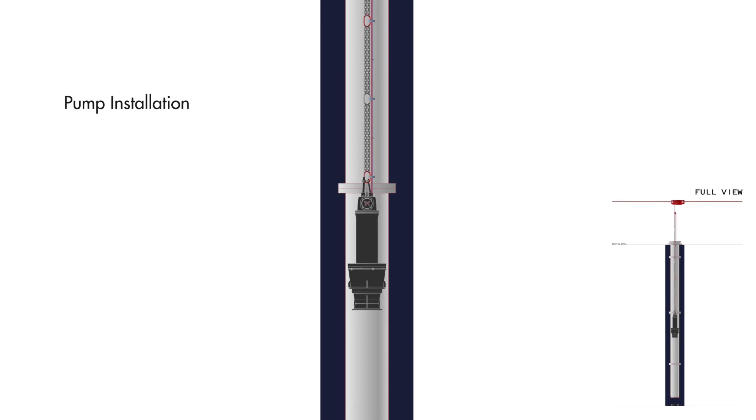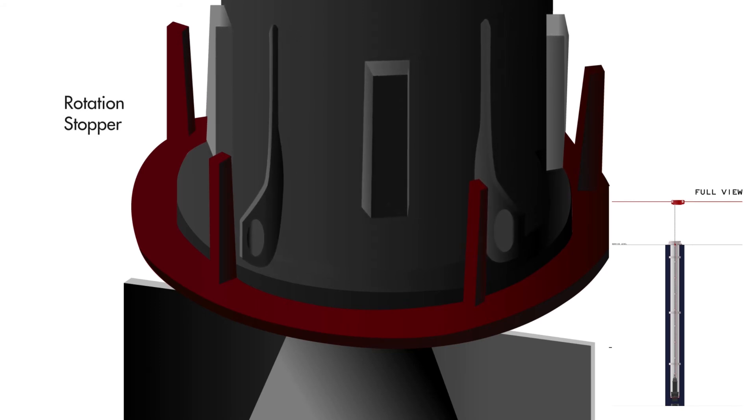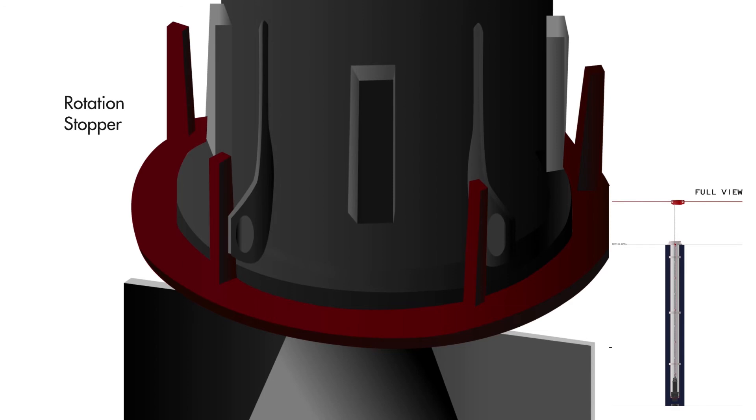With the pump almost in place on the seat ring, rotate the pump clockwise until the rotation stoppers on the suction casing and the rotation stoppers on the seat ring are against each other. Then the pump can be seated on the seat ring.